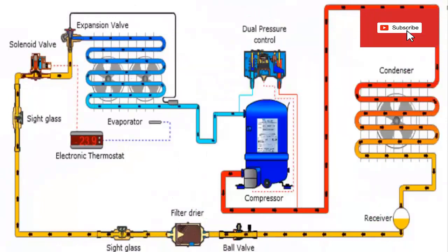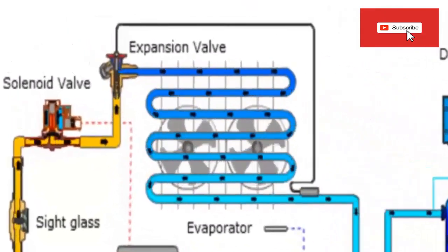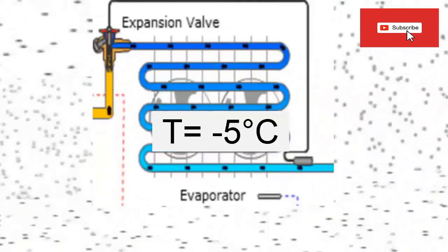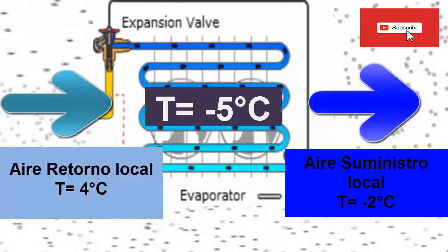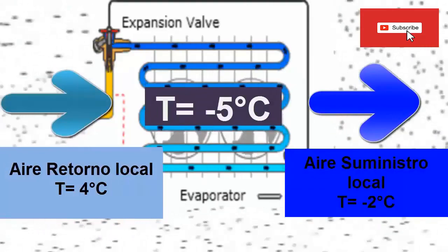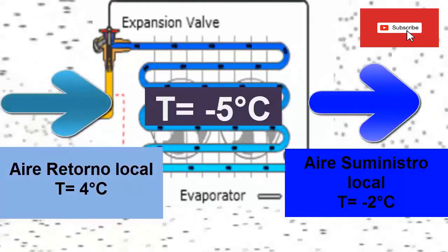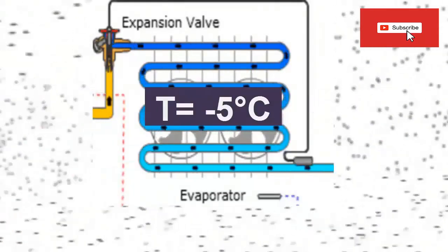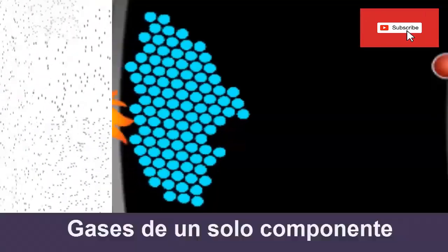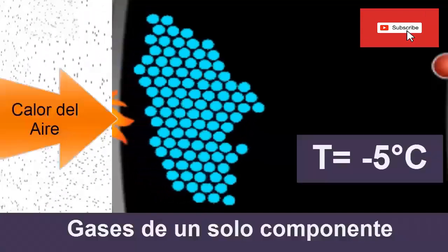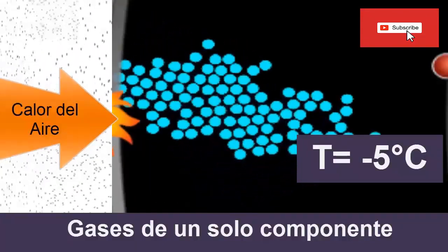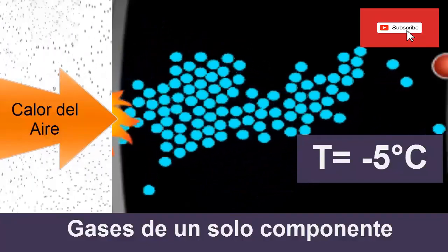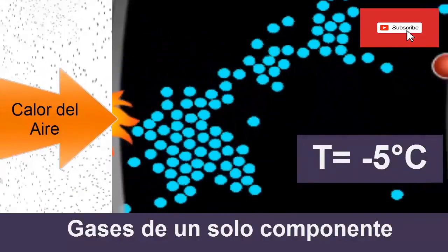The refrigerant gas in a refrigeration cycle can absorb heat from the air in a room because it has a very low temperature. In the evaporator, the heat from the air passes to the refrigerant, therefore the air loses temperature, while the heat that was from the air remains in the refrigerant, but there is no increase in its temperature because the refrigerant uses the heat to pass from the liquid phase to the vapor phase.